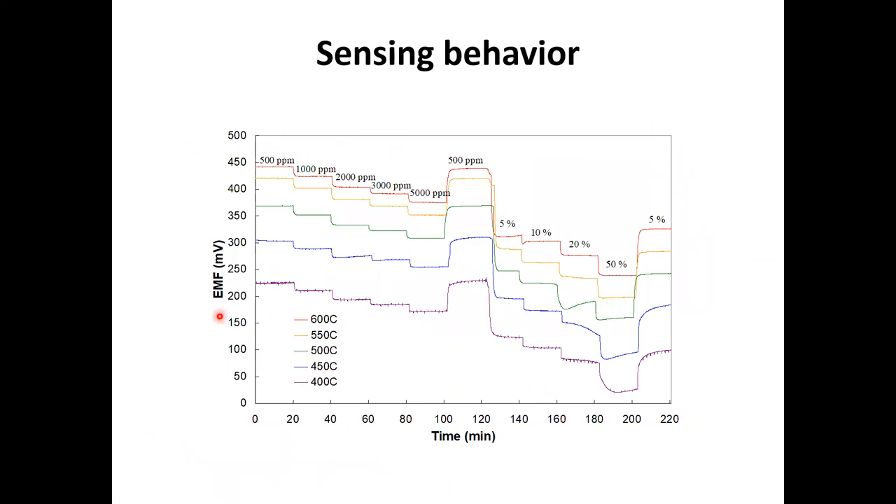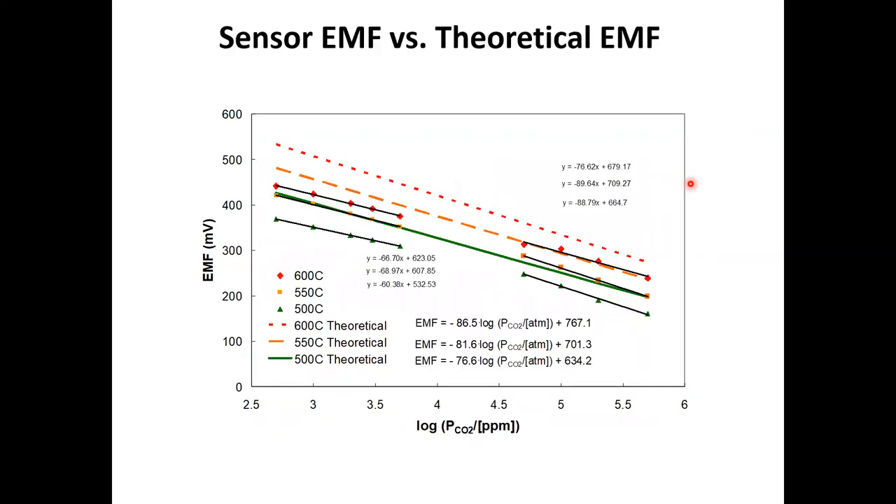Looking at the sensor signal — EMF in millivolts as a function of time — you can see responses at low concentration (PPM level) and at high concentration (percent level), at various temperatures from 400 up to 600 degrees Celsius. The calibration curve is slightly different from the theoretical value, due to electrokinetics, but it gives a linear behavior. At ppm level and at percent level, you see linear behavior. At various temperatures, you get this linear behavior of measured EMF versus logarithm of CO₂ concentration, as expected from the Nernst equation.